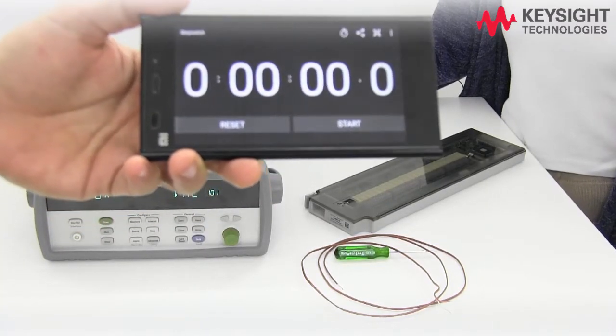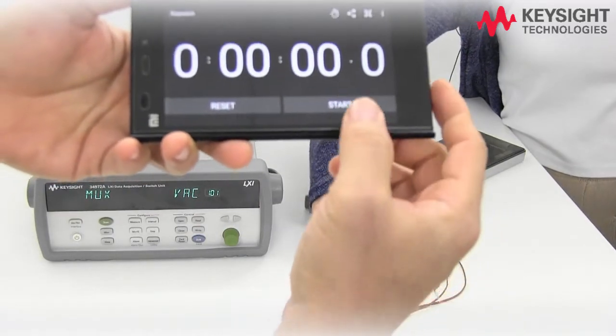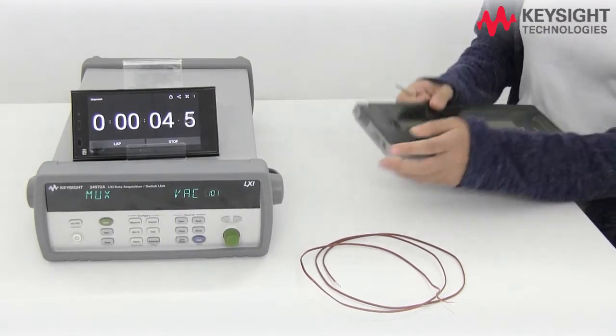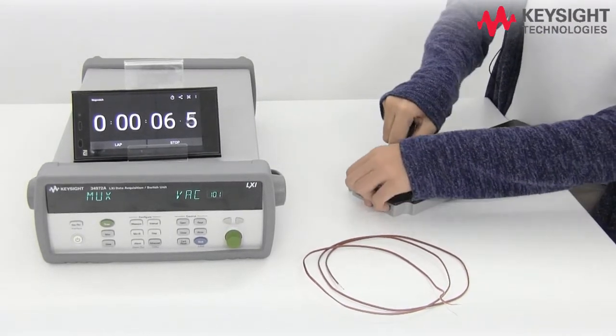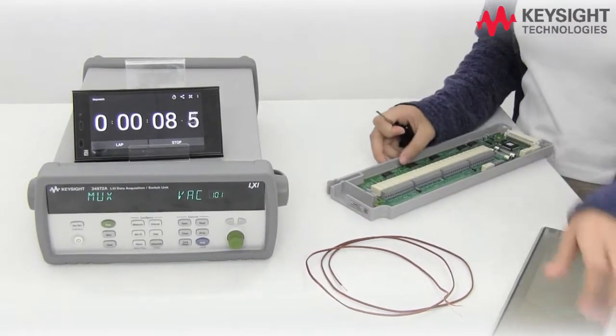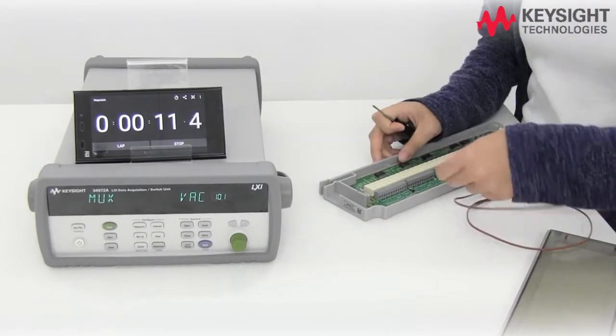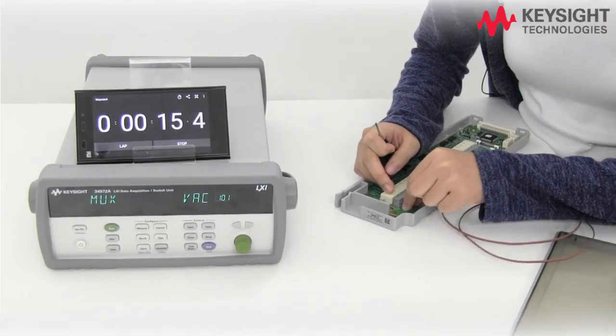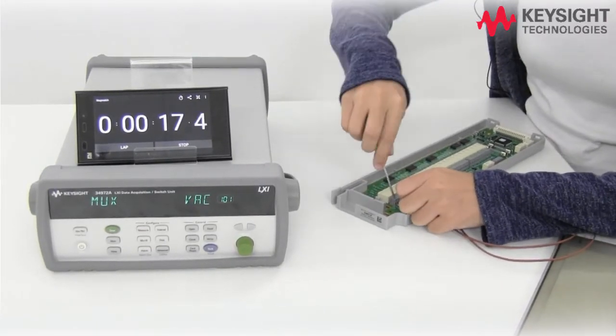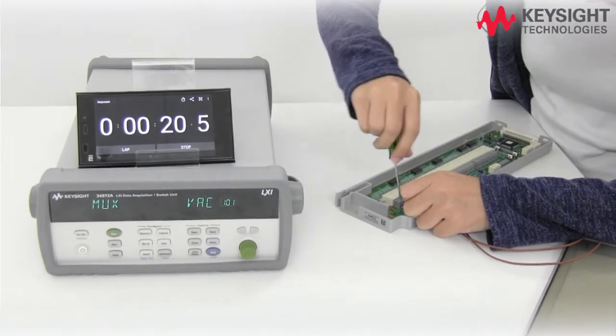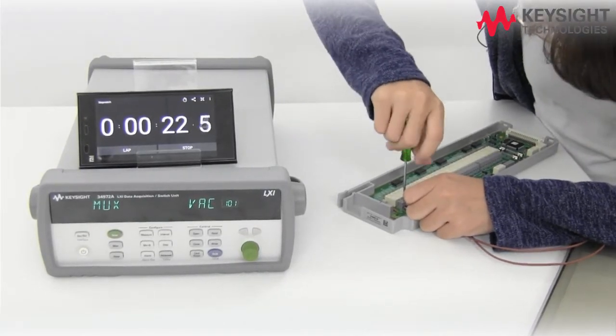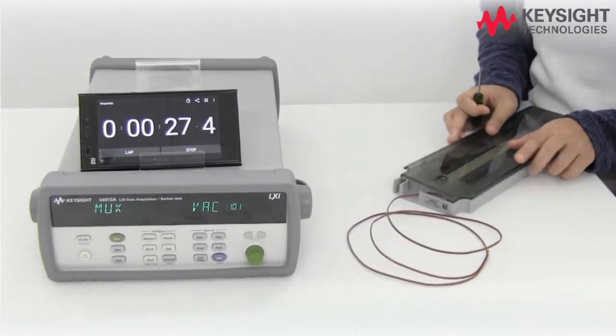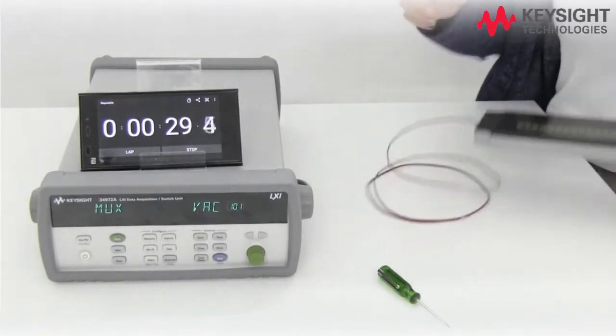Here we have the general purpose MUX card, the 34901A. Open up the cover. Now we want to connect the J-type thermocouple to channel number one. The white wire goes to high, screw this in. The red wire goes to low. Now close up the cover.